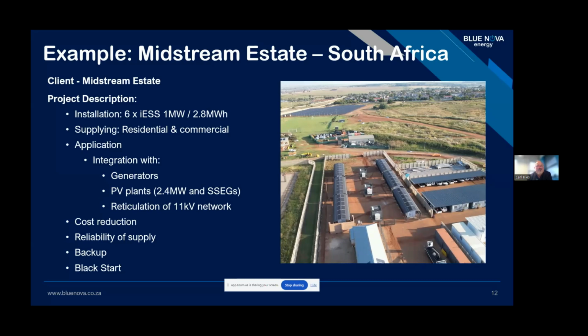So just from a sizing point of view, why 2.8 megawatt hours of storage per container? The intention is to handle 2 hours of backup for arbitrage or load shedding, which requires 2 megawatt hours. Then you've got to add losses — around 6% discharge losses, requiring 2.13 megawatt hours. And if you only discharge to 80% depth of discharge, you need 2.66 megawatt hours. So there's around 5% spare capacity, which is sufficient to compensate for state of health fade for around 2 to 4 years. And if by then the use case still makes sense, there's room to augment the batteries by adding additional strings.